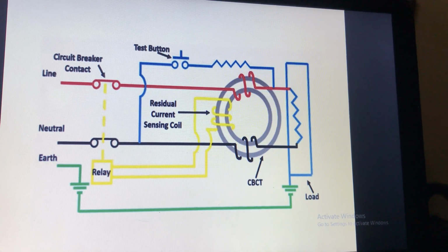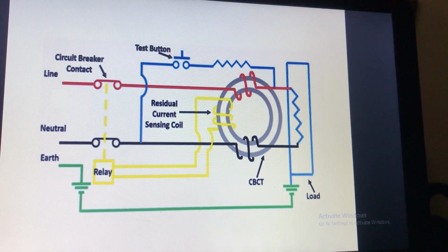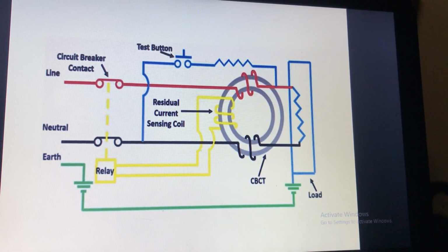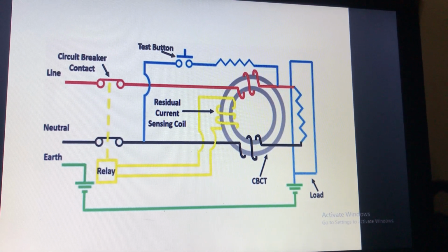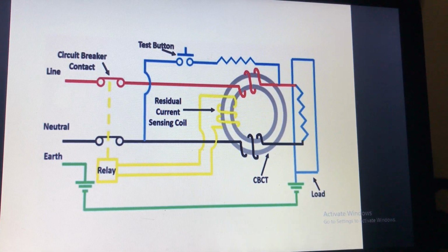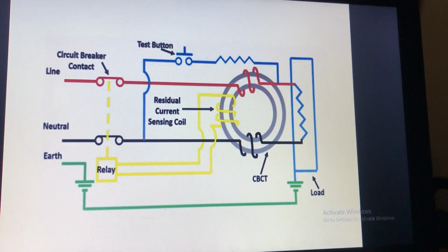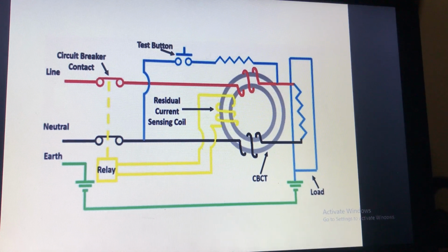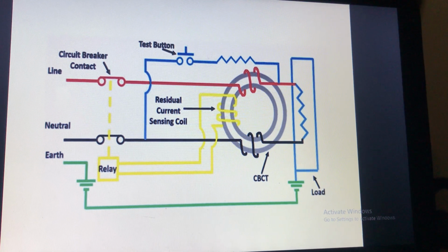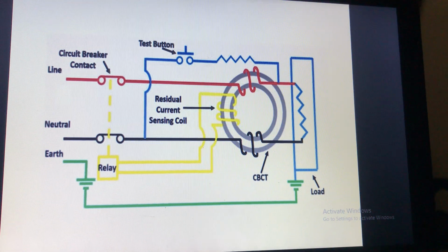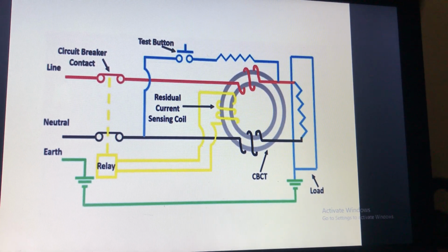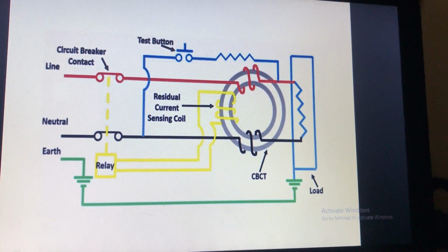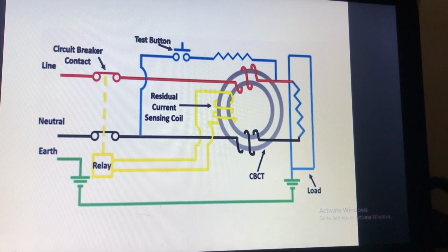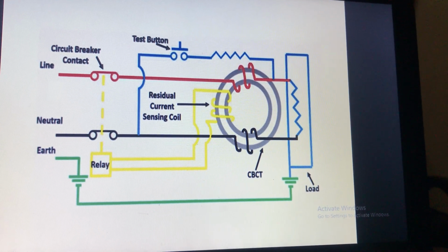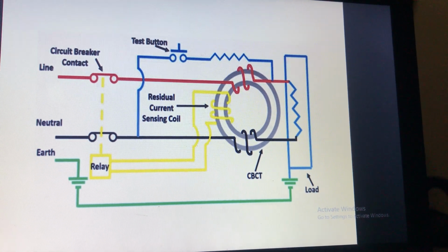Now you can see there is a test push button. If we push this button, you can see one end is connected to the neutral wire and the other end is connected to the phase wire, and there is a small resistance connected between these two ends, because by pushing this button we are short circuiting live and neutral. So there will be a short circuit, but we just want to flow some current of milliamperes just to test it. So we have connected one resistance in series with that test push button so that the current which is required should flow through the transformer core. Otherwise there will be a short circuit. So by pushing this test push button, the ELCB should get operated. If it is not operated, then further inspection on ELCB or RCCB is required.